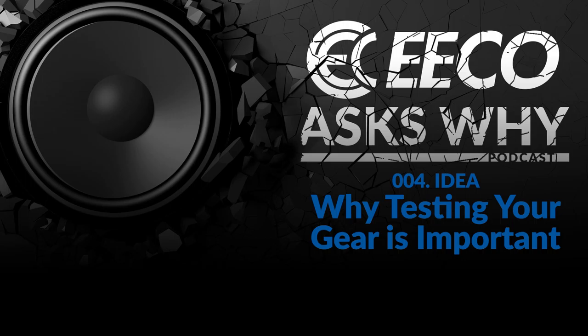And then as a last resort, when you're actually getting into troubleshooting, how does the torque look on the load cables of that breaker? How does the torque look on the line side of that breaker? Does everything appear to be mechanically sound? Because a loose connection on the cable end of that breaker or on the line side of that breaker, either one, can cause excessive heating and cause the breaker to trip. So it's not a really simple answer, but you have to start looking at a systematic approach, which includes what's the load, what are the conditions, is it well maintained?